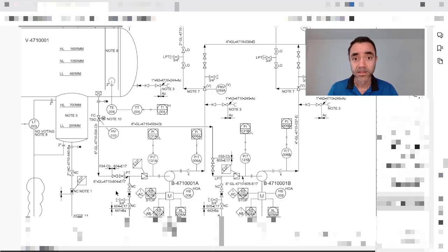The material at the top of the valve has a higher pressure rating than the material below the valve, because below the valve I am going to a blow-down system that operates near atmosphere, while in the suction of the pump I have a higher pressure, and because of that my materials must be more resistant to support the pressure inside the system.